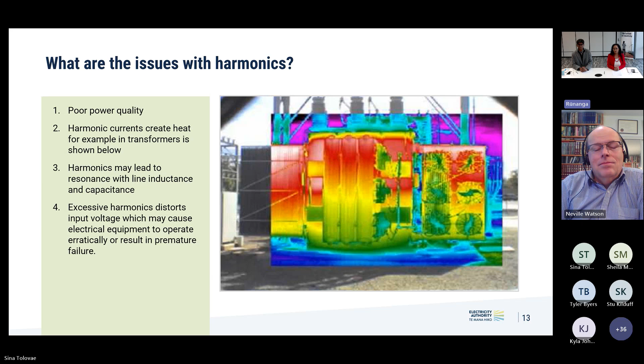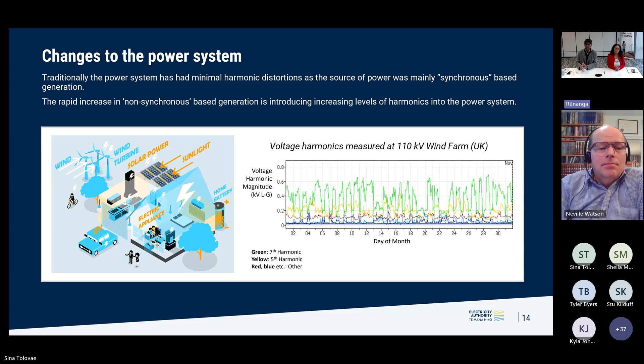And then, apart from the harmonics we have had in the past few decades, the power system has changed. We have more inverter-based generation. We have more load controllers. We have EV controllers. All of these are based on power electronics, and power electronics have switching devices. Because of these switching devices, they may inject more harmonics, or they might change the resonance in the system. They might change the network impedances. And the existing background harmonics can actually cause harm to solar farms or even inverter-based systems because they can interfere with the PLL, the phase-locked loops, and you may not have good power quality of supply from those inverter-based resources, which causes more threat to system security and reliability.